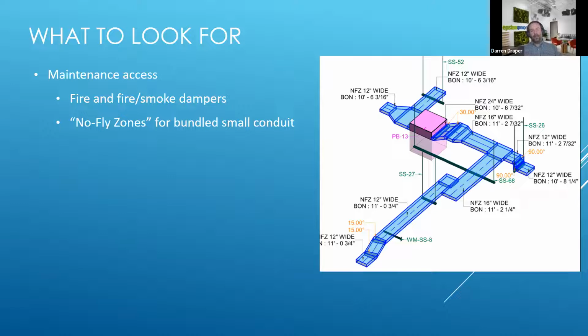But what we have seen is something similar, which I call the no-fly zone. Generally speaking, the electrical subcontractor is going to follow a path for bundled conduit, running a bunch of conduit through an area. They don't model individual pieces of conduit, but they do model a section through which conduit will fly, and that has to be avoided - hence the no-fly zone term we've heard. There may be other terms for it, but that's helpful. You see an example here, with the pull box and maintenance clearance to pull all the way down to ensure they can get back to it.